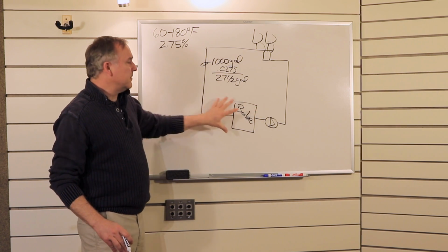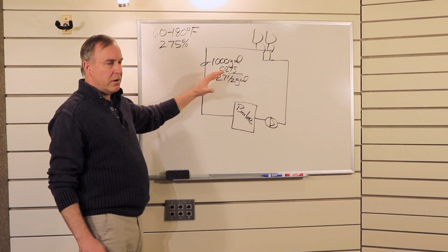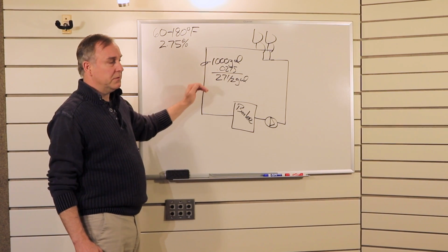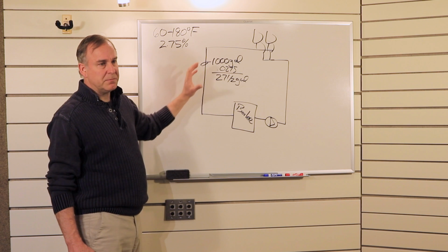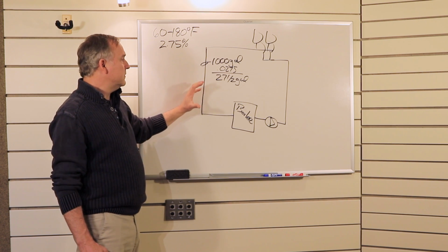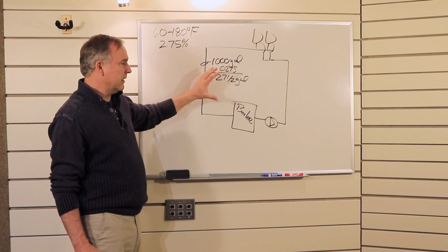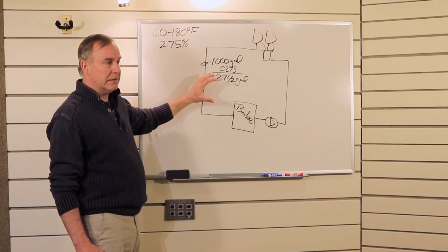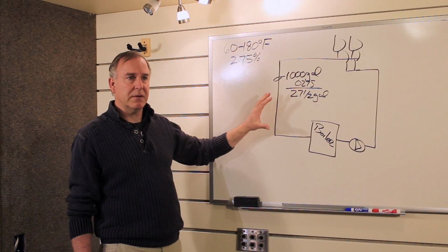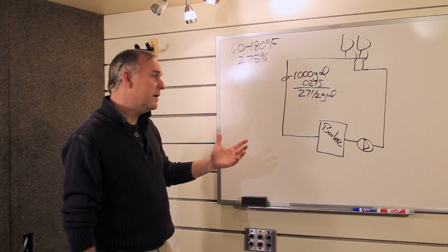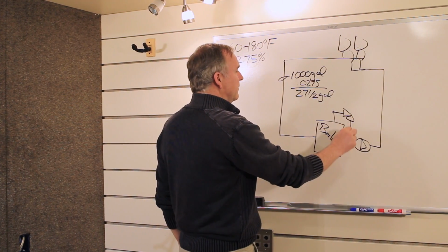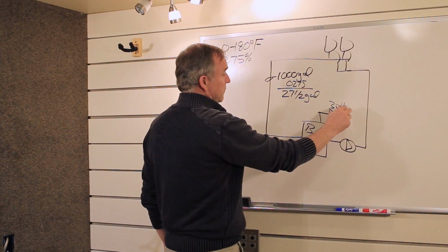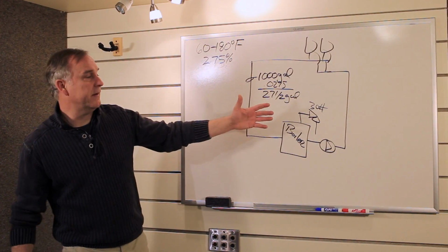Well, in the absence of some kind of relief valve, water being essentially incompressible, the pressure, even with a couple of degrees elevation here, will literally spike like crazy. So if we heat the system, we would literally break something in the system. Something's going to break. Those pressures are going to spike like crazy. So typically what's done to deal with that would be some kind of a relief valve. Or one thing that I could do to deal with this is put a relief valve on there.